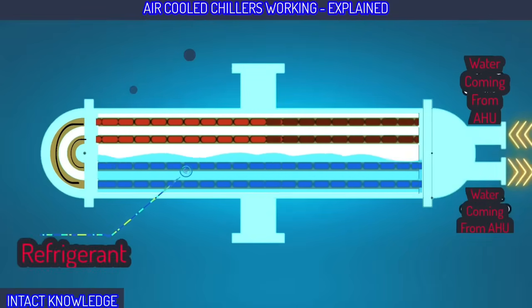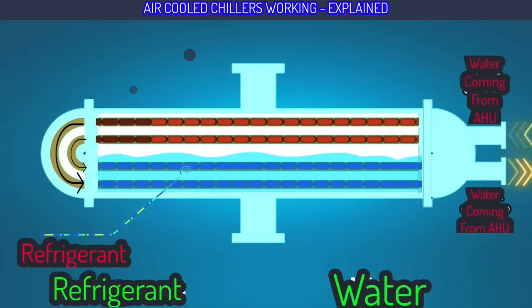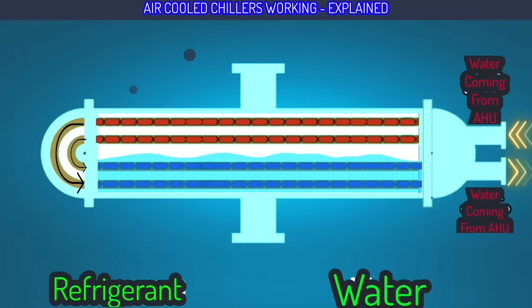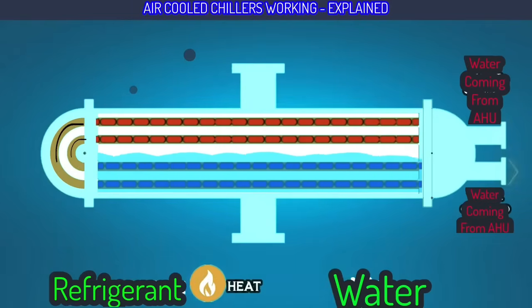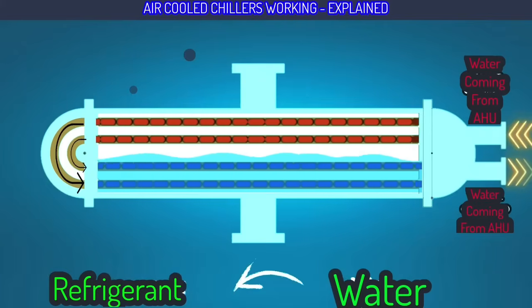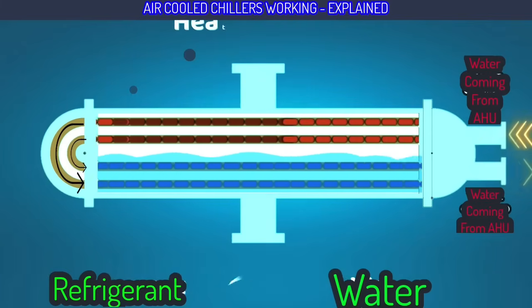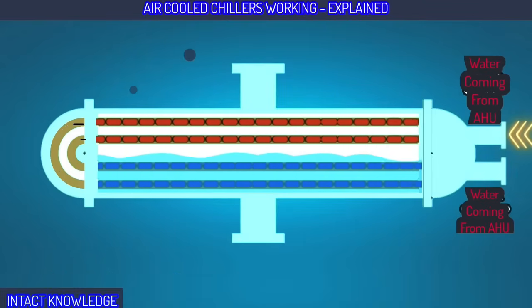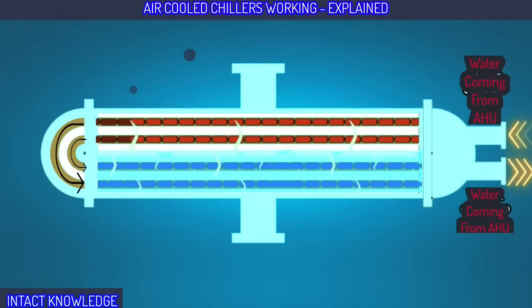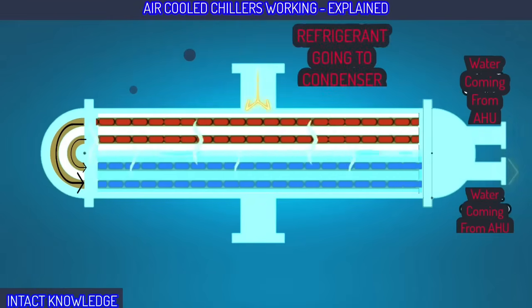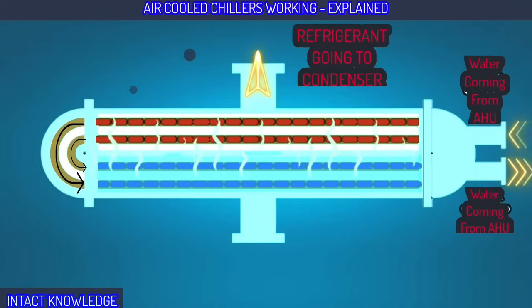The refrigerant around the coil is very cold. Being well cooled, its cooling goes to the water inside the coil. At the same time, the heat in the water goes to the refrigerant. As the heat is exchanged between water and refrigerant, we call the evaporator a heat exchanger. The boiling point of refrigerant is very low. That means refrigerant starts boiling at very low temperature. As the heat of the water is transferred to the refrigerant, it starts boiling and becomes vapor. After turning into vapor, it goes to the condenser through the compressor. The water inside the coil is thoroughly cooled and again goes to the AHU. This is the process that takes place inside the evaporator.